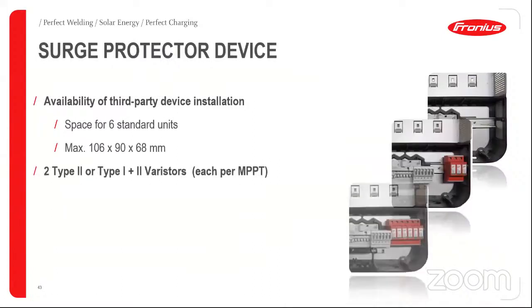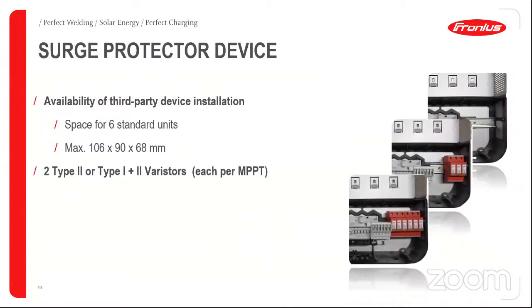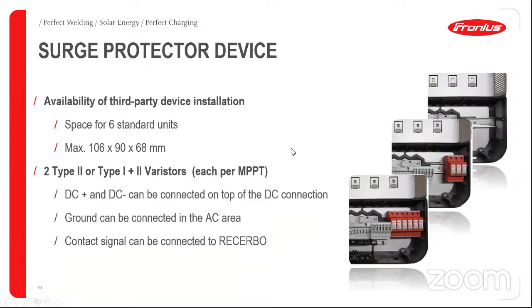Inside the inverter, we can also put our SPD. We have this space on the right side where we also have this DIN rail. We can locate two SPDs. Remember that we need one per MPP. So if in the installation two MPPs are in use, you need two SPDs. These SPDs can be type 2 or type 1 plus 2.